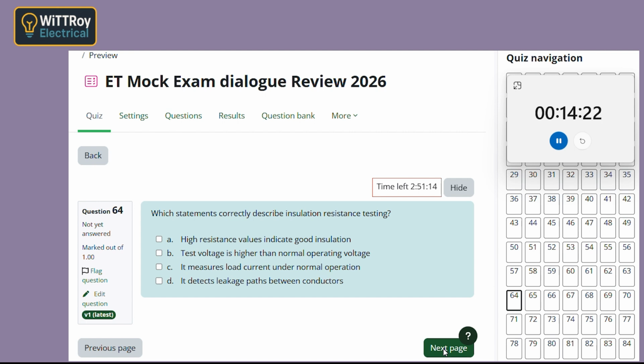Exactly. Now, the reason we use a higher test voltage is to really check the insulation properly. If there's any weakness, it shows up under that higher voltage. So it's kind of like stressing the insulation a bit. Yeah, that's a good way to think about it. And it's not measuring normal load current. That's where some people get mixed up.